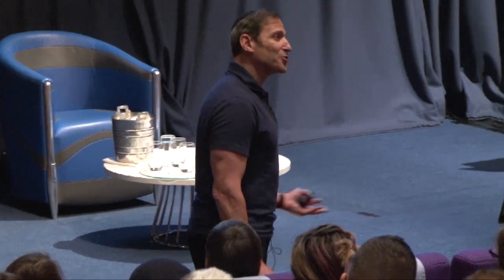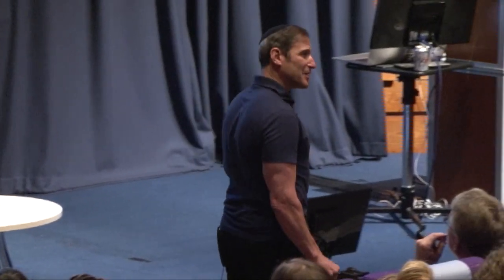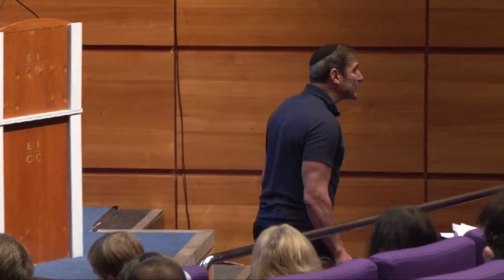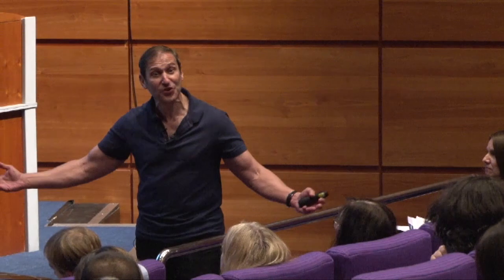But in order to know, are you irradiating any part of it? Don't tell me about the static field and stop talking to me about RF. Now we're talking about gradient stimulation. Where are your gradient energies? What's the size of your gradient coils? Left, right, front, back, up, down. Do you know? If you don't know, how do you know if you're irradiating that little star at L4, right? How do you know if you don't know where the energies are being deposited?